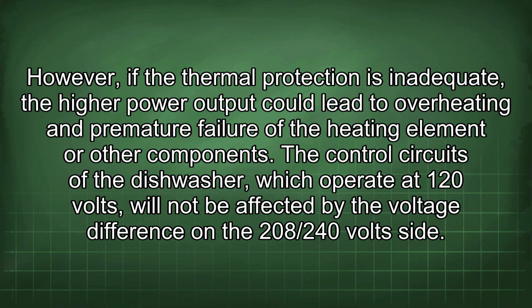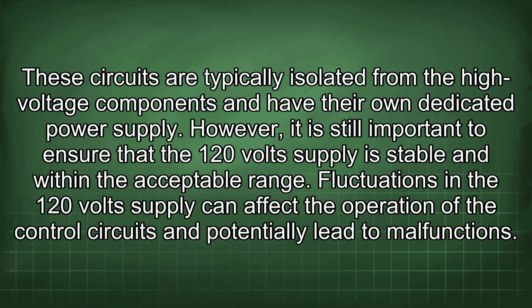The control circuits of the dishwasher, which operate at 120 volts, will not be affected by the voltage difference on the 208/240 volts side. These circuits are typically isolated from the high voltage components and have their own dedicated power supply. However, it is still important to ensure that the 120 volt supply is stable and within the acceptable range. Fluctuations in the 120 volt supply can affect the operation of the control circuits and potentially lead to malfunctions.